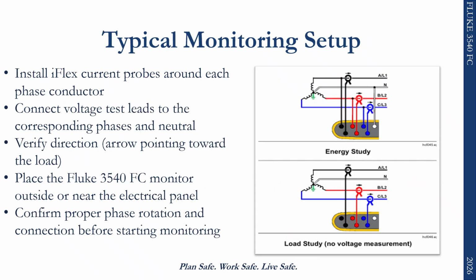A typical monitoring setup begins by installing the iFlex current probes around each phase conductor. Voltage test leads are then connected to the appropriate phases and neutral. It is important to verify that the arrow on the current probe is pointing toward the load. The monitoring unit is placed outside or near the electrical panel, and proper phase rotation and connections should be confirmed before starting the monitoring process.